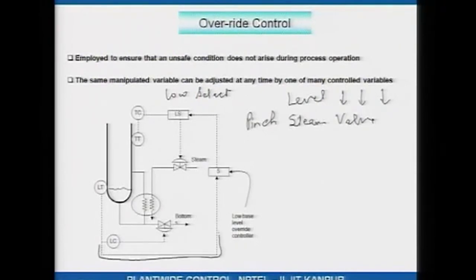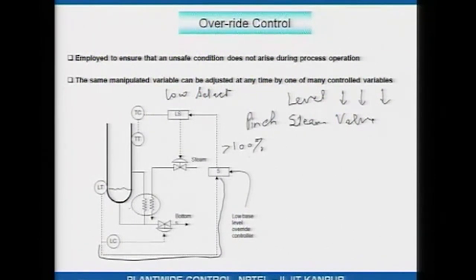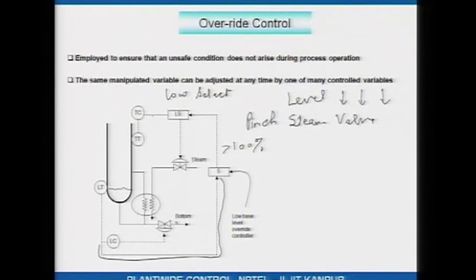Ordinarily the steam valve is moved to hold a tray temperature constant, but should the level go below a threshold and continue to go down, you would like the steam to come under level control. This is implemented as follows: here is the level signal. You multiply the level — say level is 50 percent — by 5. If the level is not too low, this signal will usually be greater than 100 percent. If the level goes down to 20 percent, 20 percent times 5 is exactly 100 percent. If the level further goes below 20 percent, this signal will go below 100 percent.